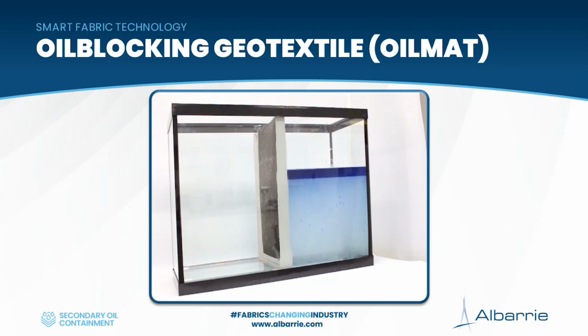Once that high concentration of oil hits the mat, it starts to gel and seal the mat, containing the high concentration of oil. After a catastrophic failure with oil pooled in the containment, you do have to take steps to remediate it. If you leave it, the oil will stay there but start collecting everything else—if it rains again, the water will start pooling in it too, as shown in this video. But it does give you the ability to contain that passively, without any instrumentation or people having to do anything.